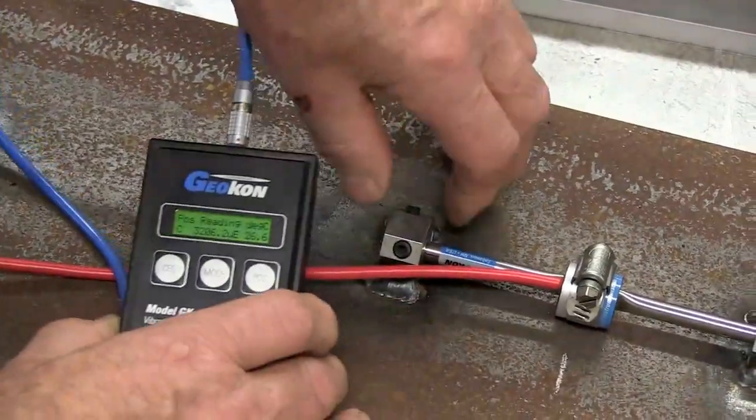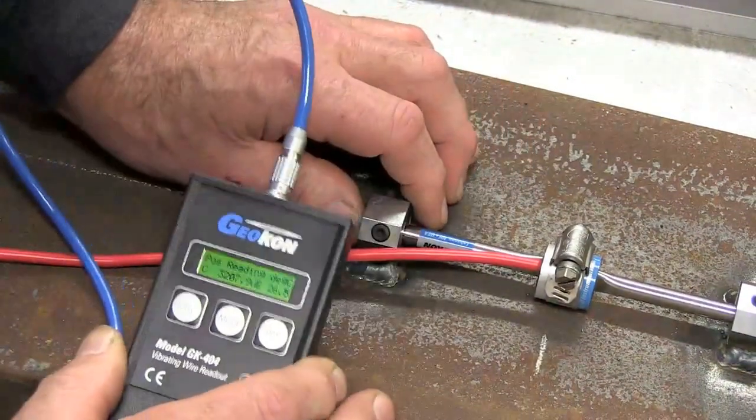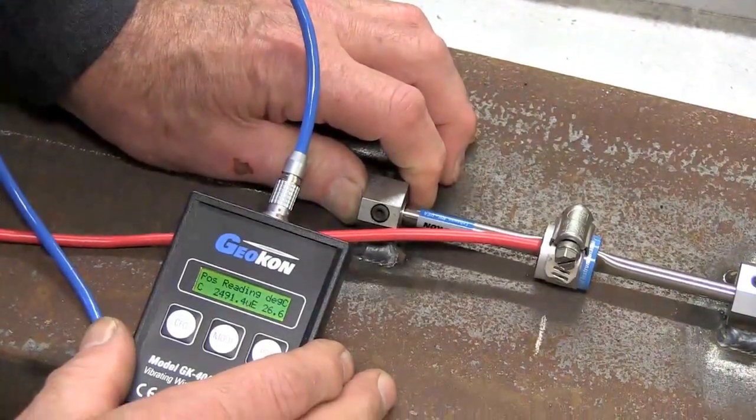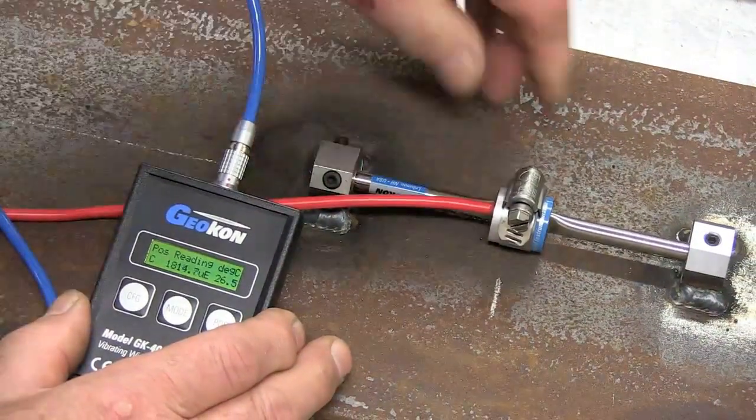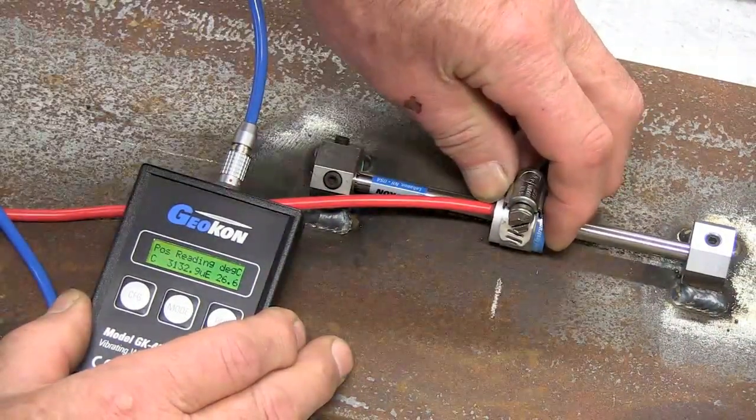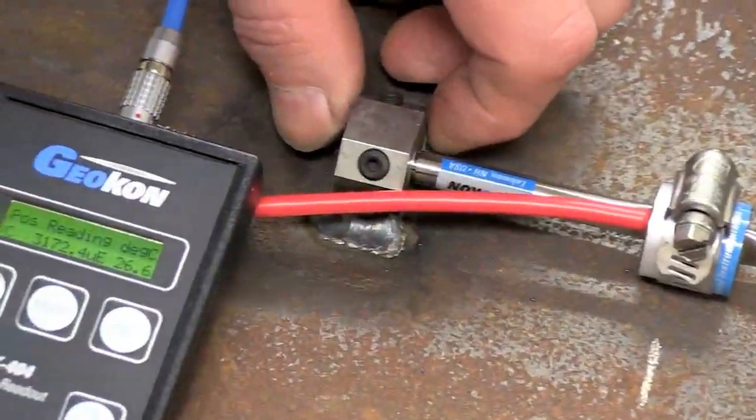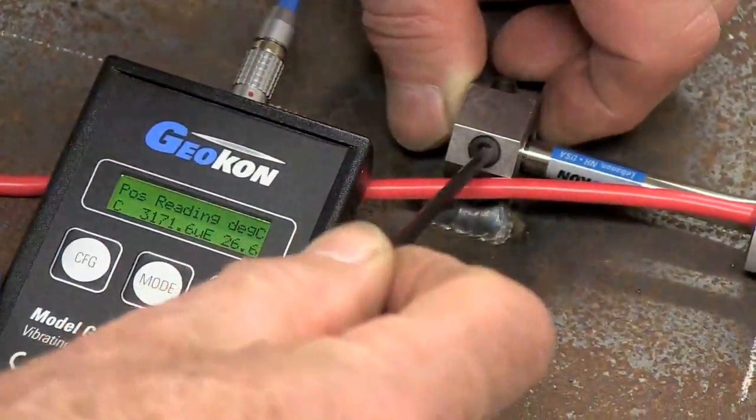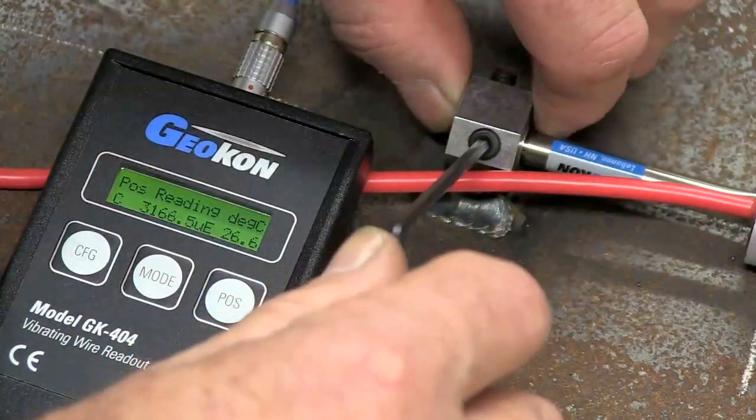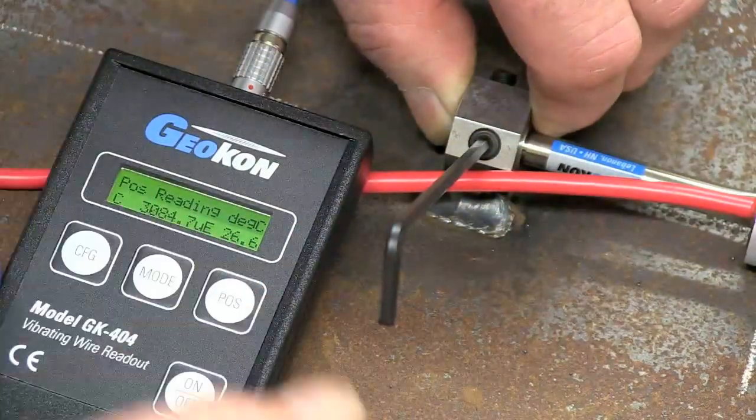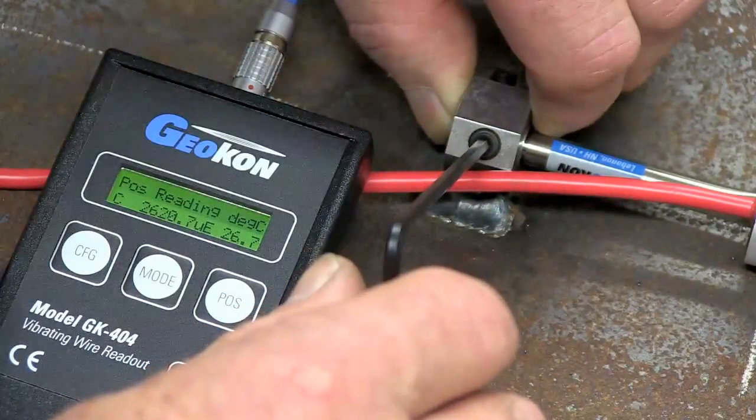The way we do that is we put a force either through the end of this gauge, if you can see the reading changing, or by pushing or pulling on this coil. In this case, I think I'm going to use the end of the gauge. Then, you tighten, alternately, these set screws. The first thing you do is try to get a steady reading of 2,500 microstrain.